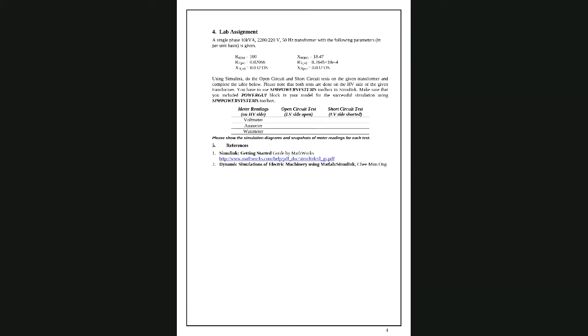Once it's built, we need to record 3 parameters for each test: the open circuit test and short circuit test. We use these tests on the low level side, which is the secondary - low level means secondary winding, high level means primary winding. We have to take those measurements on the high level, high voltage side.